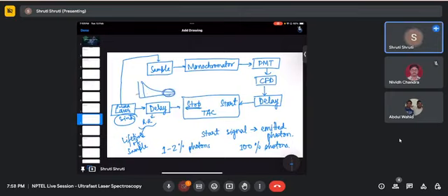this red one is my fitted data. How good the fitting is, is defined by the chi-square. Chi-square should be more than 1 and near to 1. The maximum for a good fit we consider is a chi-square of 1.1 to 1.5, at max 1.5. More than that it is a bad fit.